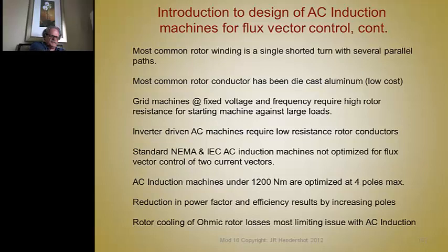The other issue involved with these machines, as we'll see when we have a look at the torque speed curve, is the starting torque. One of the characteristics of an induction machine is that if you drive an induction motor on a fixed voltage and frequency, and you start it with instant voltage and instant full frequency, without ramping the frequency up, then your starting torque is very low if you have a low resistance rotor. What you want is a high resistance rotor for starting, and that gives you a high starting torque.